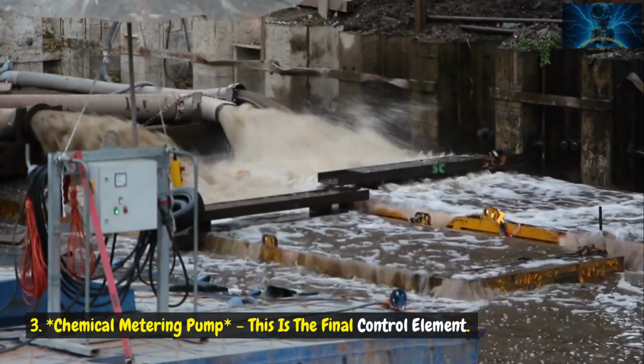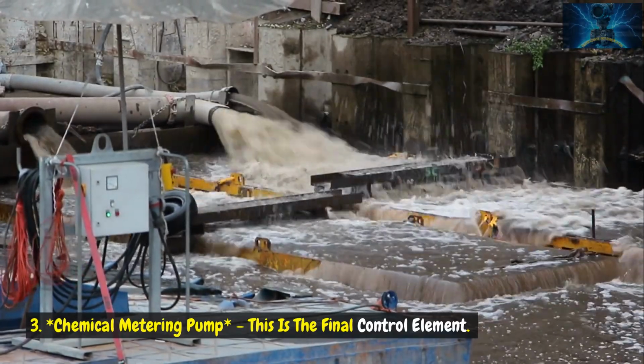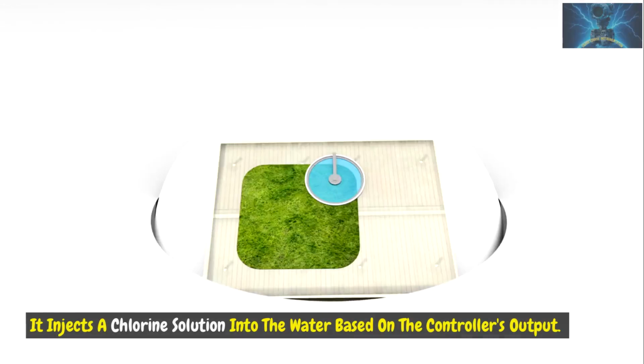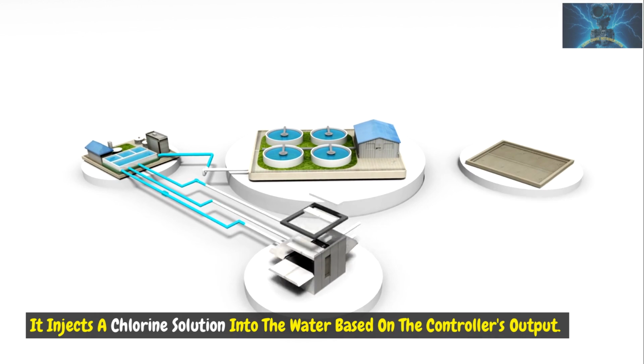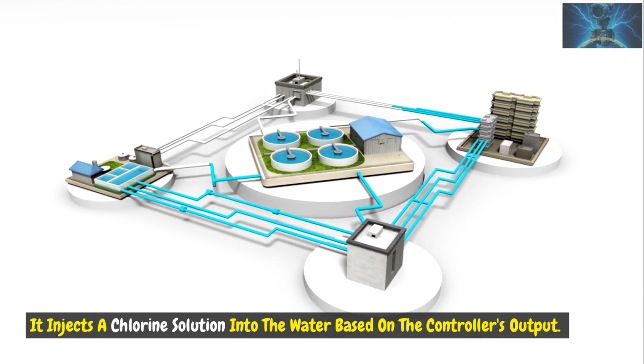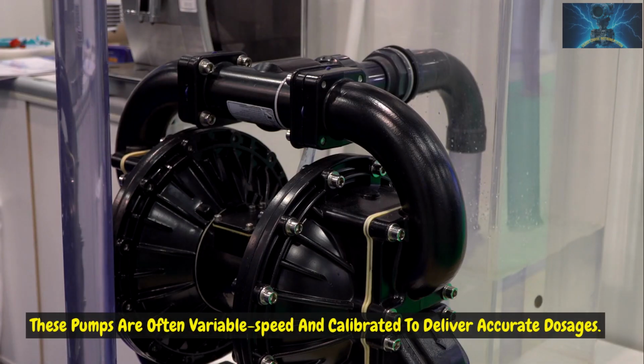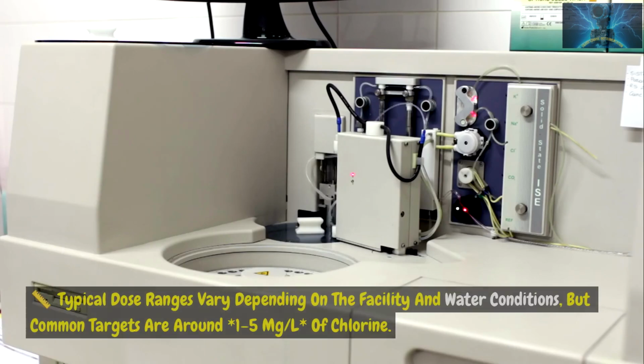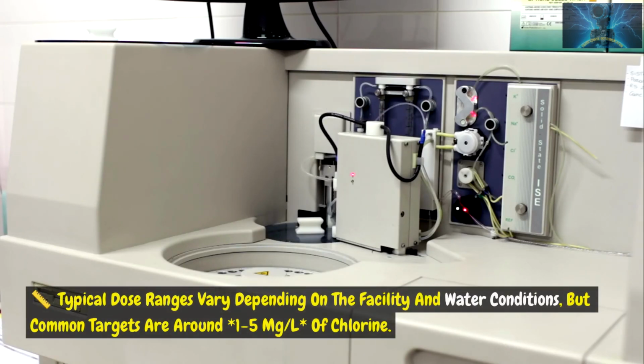3. Chemical metering pump. This is the final control element. It injects a chlorine solution into the water based on the controller's output. These pumps are often variable speed and calibrated to deliver accurate dosages.